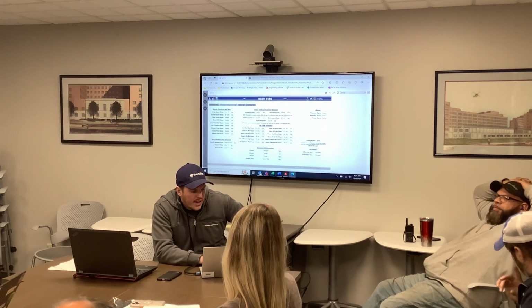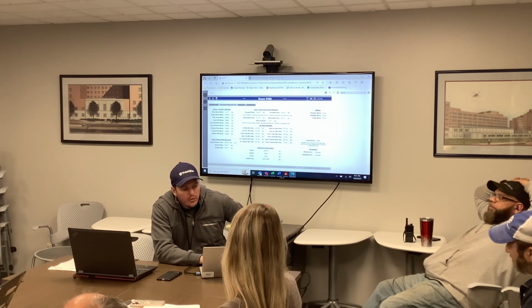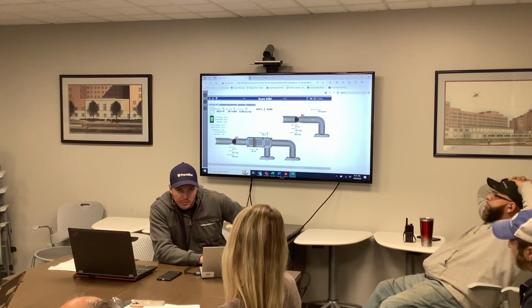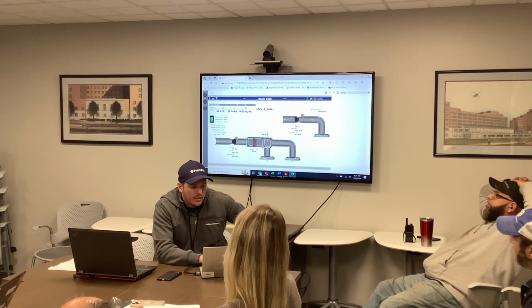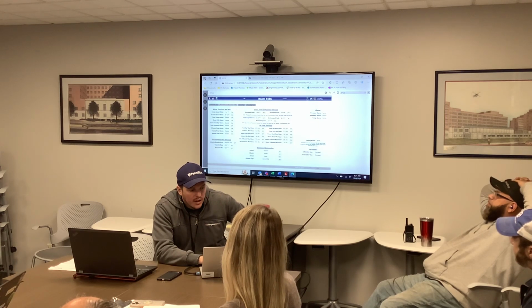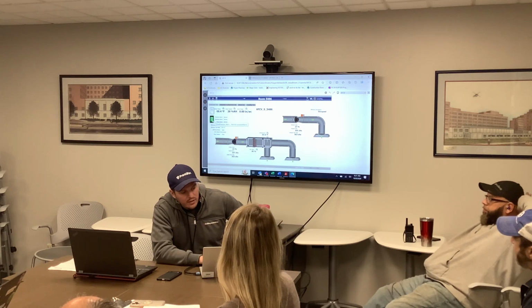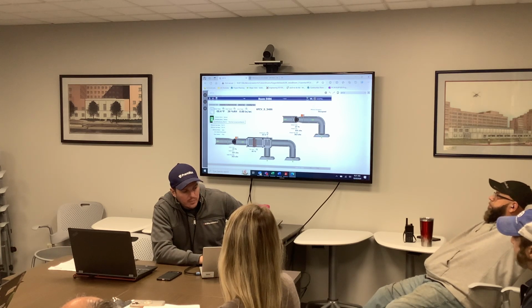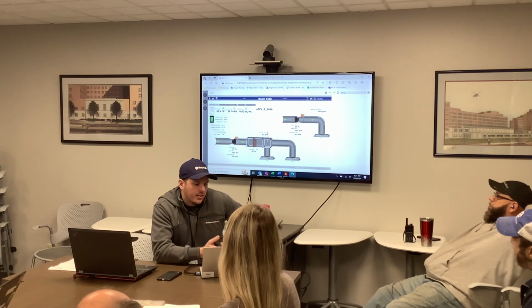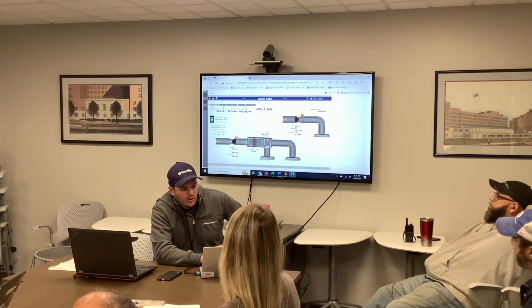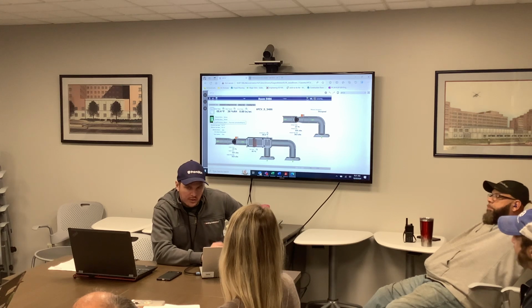So I'm just realizing now I don't have it on here, but at the local sensor, you can say I want this room positive pressure, negative pressure, or neutral pressure, and you can set a set point on it. And that's through the display. Each one of these airflow valves has, on the outside of the room, your monitor, and they actually have a space temperature sensor in the space. So when I'm talking about the isolation, if you want to do a negative, positive or neutral pressure, you would do it through this sensor, the display.